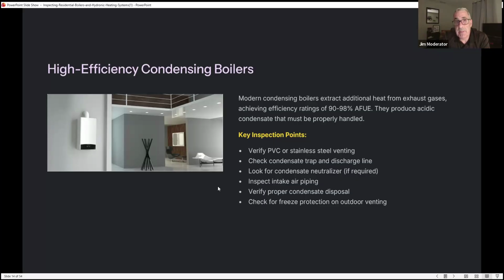It's the same kind of inspection I do with the boiler. I will look for the neutralizer. I also check for proper condensate disposal. Now, if it's a septic system, I've been in enough inspections where if I've lined 20 septic guys up, 10 will tell you that they don't want the condensate going into the septic system, and 10 will tell you it's fine. And the 11th will tell you it's okay that it's draining right into the ground. So I just want to make sure it's draining someplace and it's not going to back up.